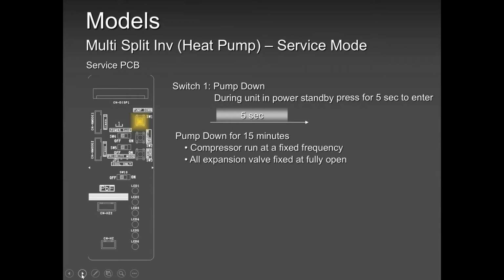So while the compressor is pumping down, recovering all the gas from the indoor units, be ready to shut your suction line, okay guys, because your liquid line is already shut using your Allen key. So pump down will start, the compressor will run at a fixed frequency, all the expansion valves will be fully open, and all the indoor units will run in forced cooling operation.